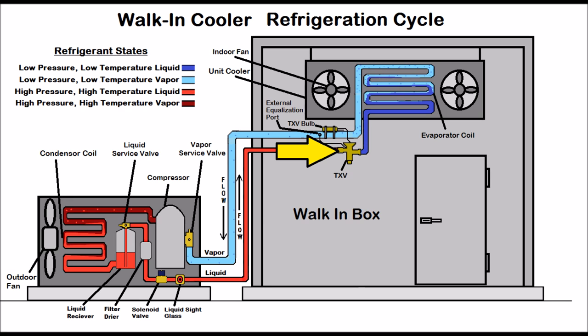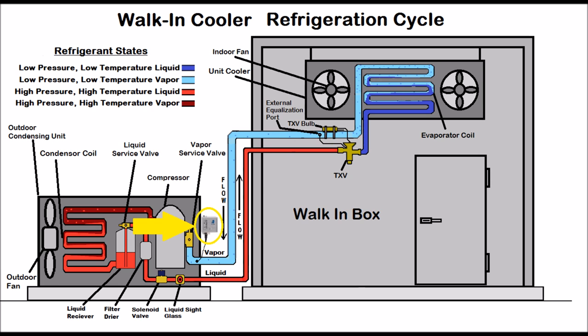The thermostatic expansion valve is reading the superheat and trying to maintain it. In a walk-in box, you're looking for about six to eight degrees of superheat once the temperature inside is lower. The superheated, low pressure, low temperature vapor refrigerant leaves the walk-in box and heads back to the outdoor unit. You may have a low pressure control mounted on the suction line before it goes to the compressor. Then the low pressure, low temperature vapor refrigerant heads back into the compressor and the cycle starts all over.